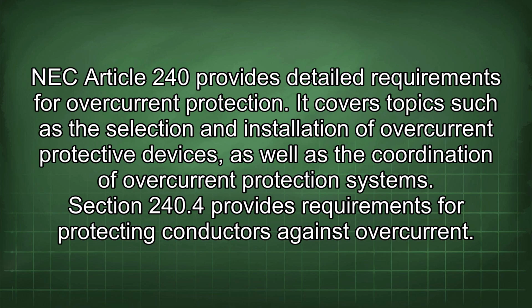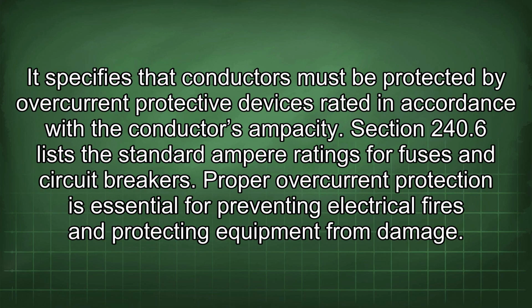protection systems. Section 240.4 provides requirements for protecting conductors against overcurrent. It specifies that conductors must be protected by overcurrent protective devices rated in accordance with the conductor's ampacity. Section 240.6 lists the standard ampere ratings for fuses and circuit breakers. Proper overcurrent protection is essential for preventing electrical fires and protecting equipment from damage.